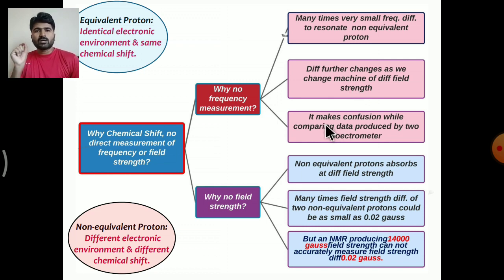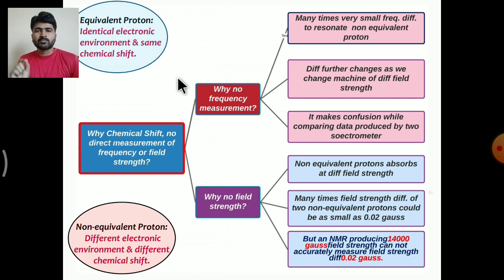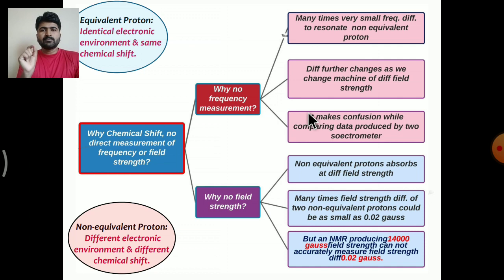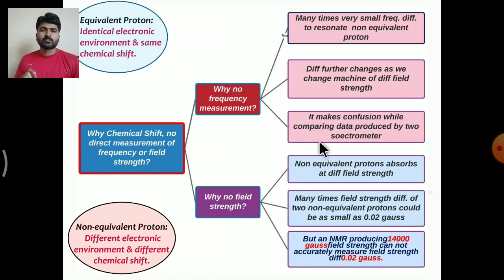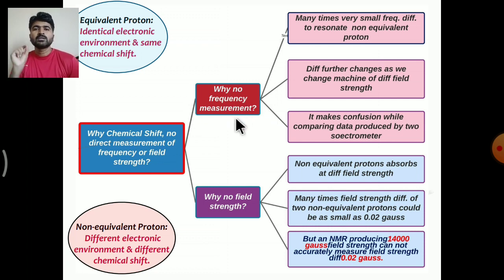Another issue is that data produced by one machine for the same proton differs from data produced by another machine, which creates confusion while comparing data produced by different spectrometers. Therefore there is no direct measurement of the frequency required to resonate the proton.